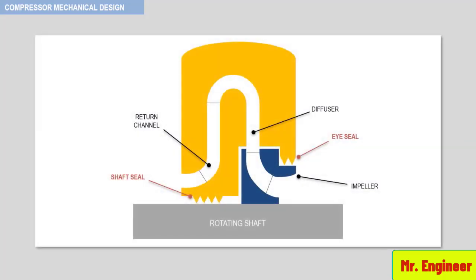Each impeller diaphragm contains one eye seal and one shaft seal. These seals are designed to minimize leakage from the diffuser to the inlet of the impeller and to the inlet of the next stage.